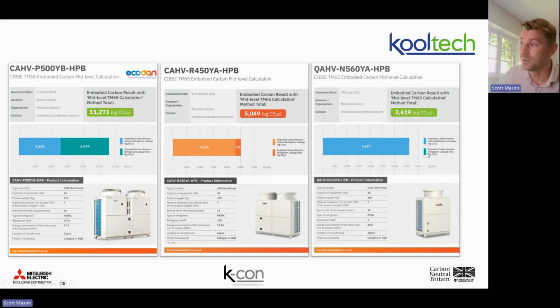But the embodied carbon, your refrigerant GWP, is 1. So on a hot water application, not only can we enhance the operational carbon and the system efficiency and the embodied carbon, we can also make the application easier. And that's because, remember, we've got a 50-degree delta T, not a 5. So I'm using 1-inch pipework. So yeah, there's a lot of benefits to this little unit, which is why if you had a heating circuit, we try and lead with CAHV. If you've got hot water, we lead with QAHV. And if you've got combined, it's a CAHV doing that combined application.